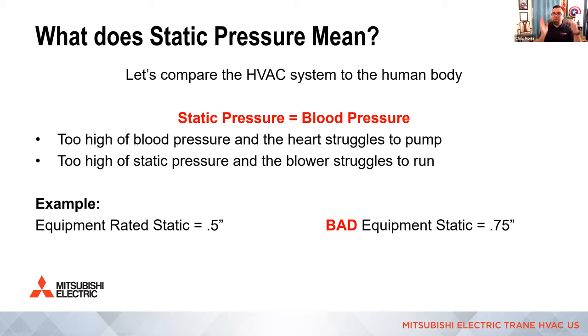Not just one side, both sides, and you add them together, right? So supply plus the return. Now, if there's a big imbalance, that would be really easy to know where the problem is. So as an example, if I had 0.1 static pressure on the supply, and in this example on the bad, negative 0.65 on the return, oh my gosh, my return's really restricted. Let's find out what's going on.